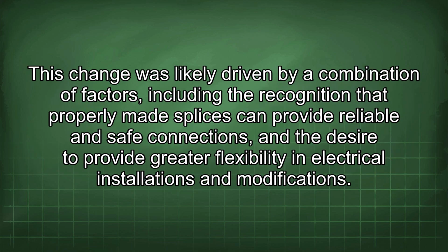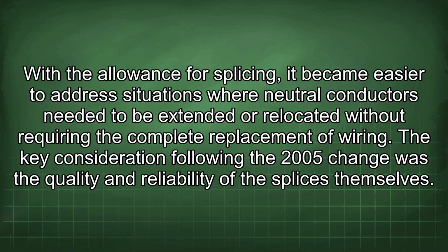This change was likely driven by a combination of factors, including the recognition that properly made splices can provide reliable and safe connections, and the desire to provide greater flexibility in electrical installations and modifications. With the allowance for splicing, it became easier to address situations where neutral conductors needed to be extended or relocated without requiring the complete replacement of wiring. The key consideration following the 2005 change was the quality and reliability of the splices themselves.